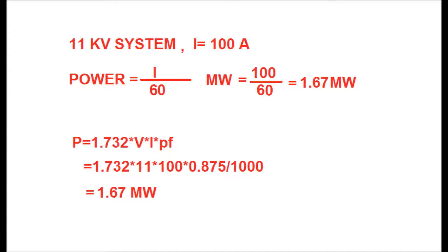We know that power P = √3 × V × I × cos φ, where cos φ is the power factor. Taking power factor as 0.875, you get P = 1.732 × 11 × 100 × 0.875 divided by 1000, which gives 1.67 megawatts.